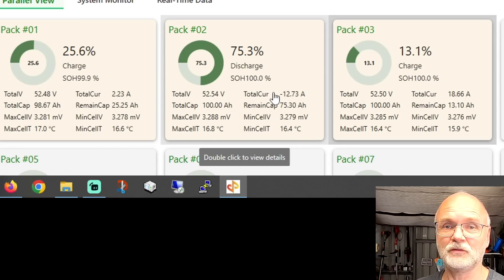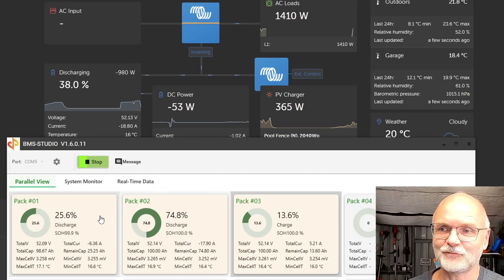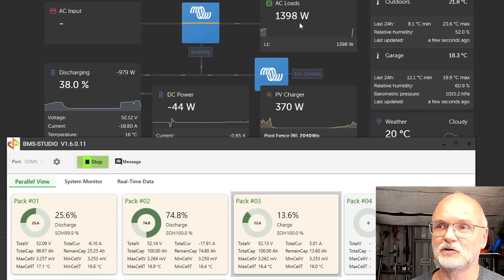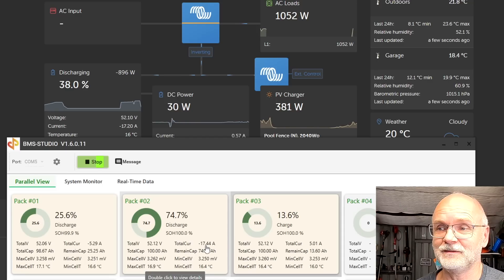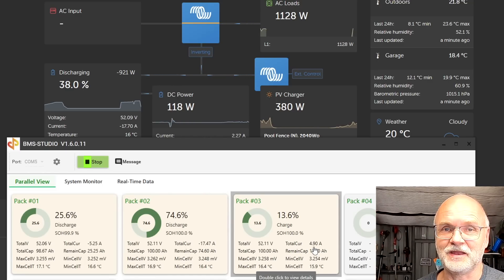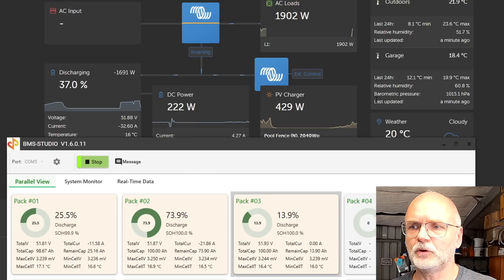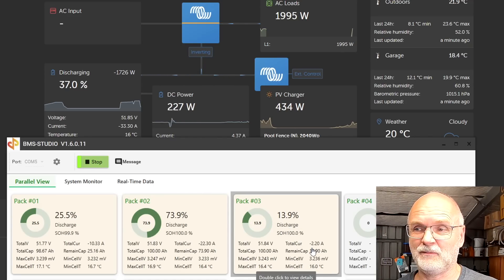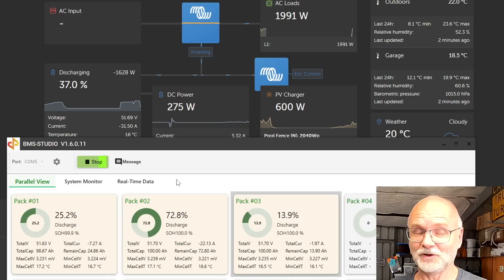Now I want to introduce a load. I'll turn on the Phoenix inverter. Here we can see the dynamics of such a system — we've got solar power, three batteries with different states of charge, and a 1.4 kilowatt load connected. Battery number one gets discharged with 5 amps, battery number two has almost 18 amps coming out, and battery number three is actually getting charged with 4.9 amps. Let me double the load — two kilowatts now. Battery number three, our lowest, is doing almost nothing: zero amps. The majority of power comes from pack two, the highest state of charge, with some energy from battery one.